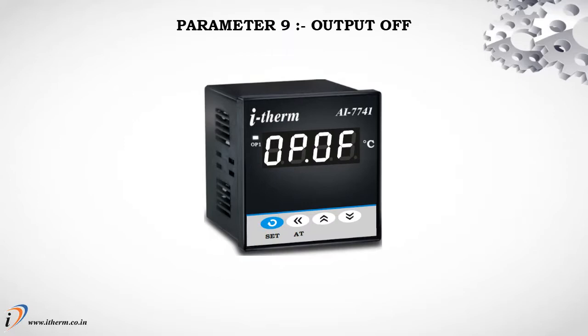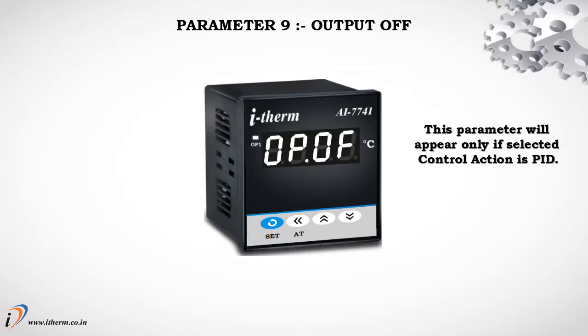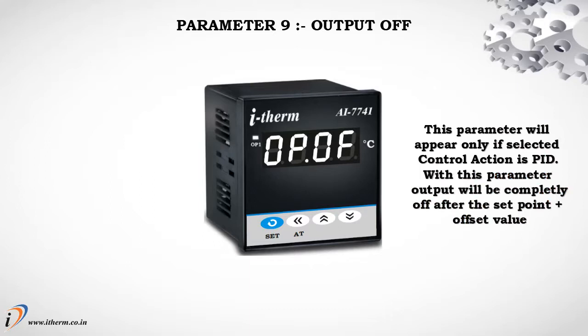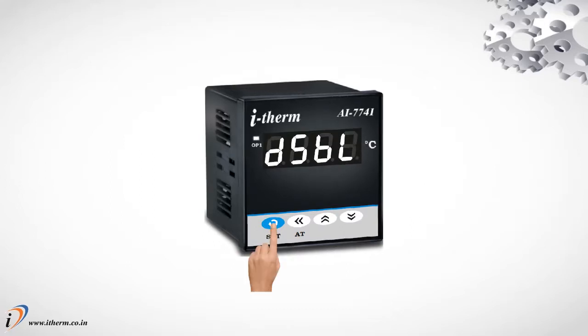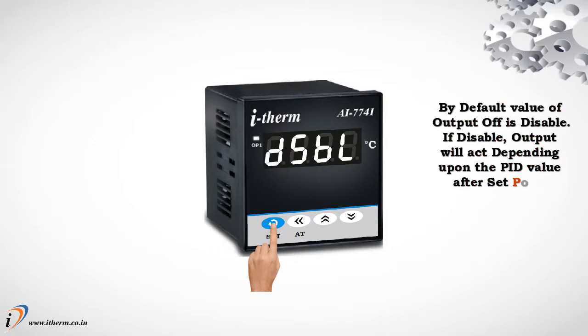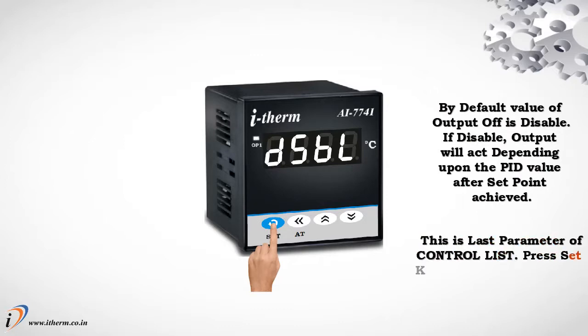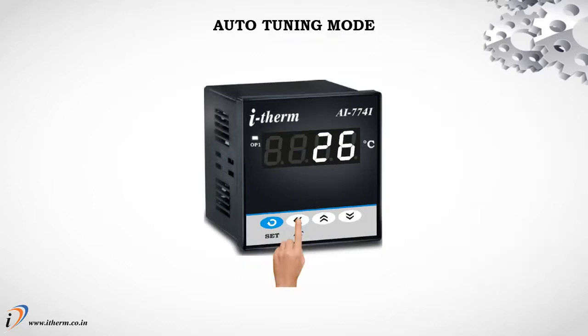Parameter 9, output off. This parameter will appear only if selected control action is PID. With this parameter, output will be completely off after the set point plus offset value. By default, value of output off is disable. If disabled, output will act depending upon the PID value after set point achieved. Default set point offset value is 0. This is the last parameter of control mode. Press Set key to enter in auto-tuning mode.